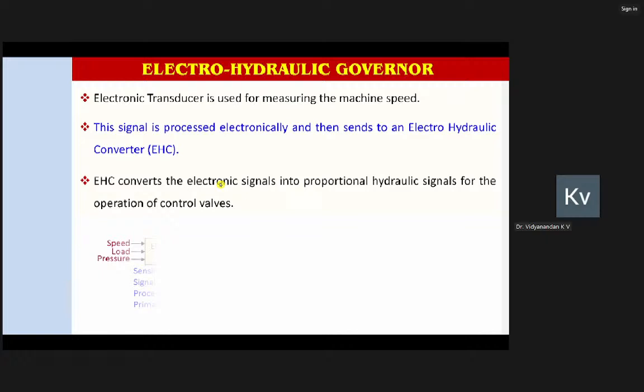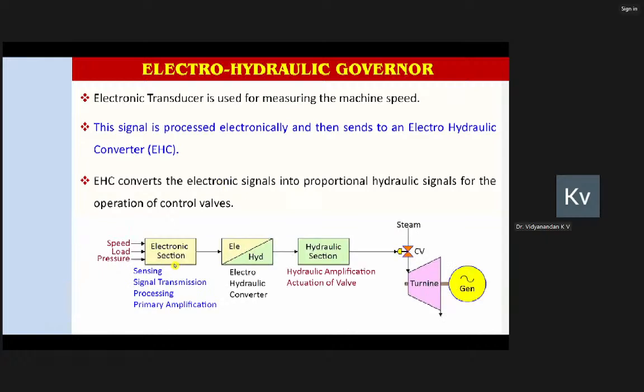So the advantage of the electro-hydraulic governor is this: the hydraulic governor was a single loop controller, because it was effectively a speed controller, just a simple controller. But as we know, once the unit is synchronized, a speed controller is not a very efficient and effective control as far as load controllability is concerned for supporting the grid. So it is very difficult to regulate the frequency using the hydraulic governor. With the introduction of the electro-hydraulic governor, more control features were incorporated over and above the speed controller. They incorporated load control, pressure control, and whatever is required, that is possible, because imagination is the only limit. Otherwise, everything is possible. This happened after the 1950s.